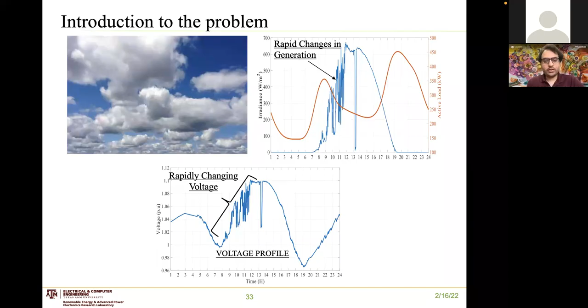The red curve is the voltage at the same location with distributed generation. As soon as the DG turns on, the voltage at that point increases, and there's increased variability as well. This happens until the DG stops generating power, and when it turns off, the two curves meet.